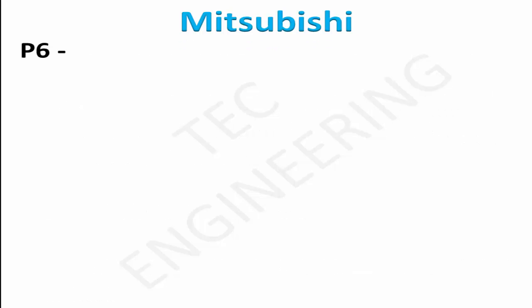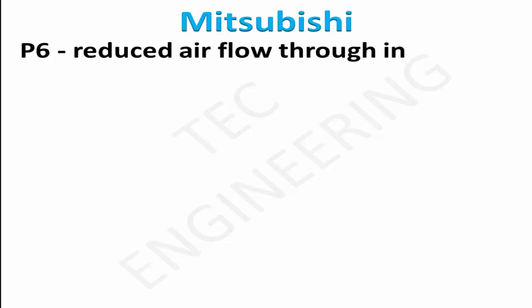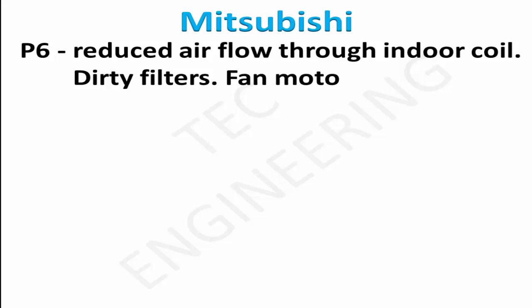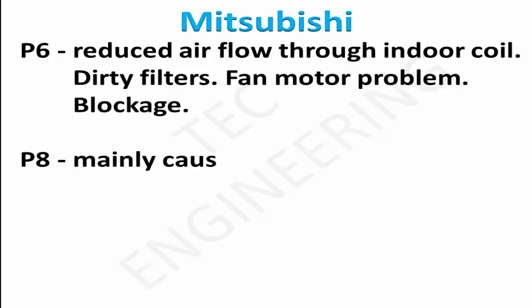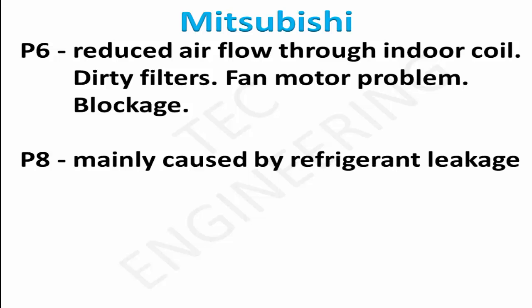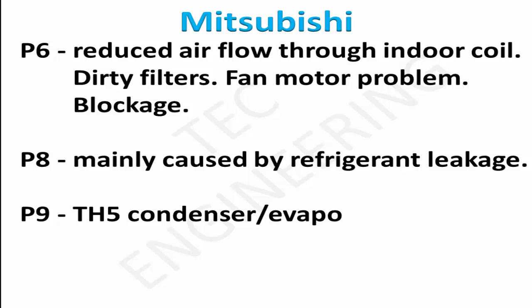P6: reduced airflow through indoor coil — dirty filters, fan motor problem, or blockage. P8: mainly caused by refrigerant leakage. P9: TH5 condenser/evaporator thermistor open circuit.